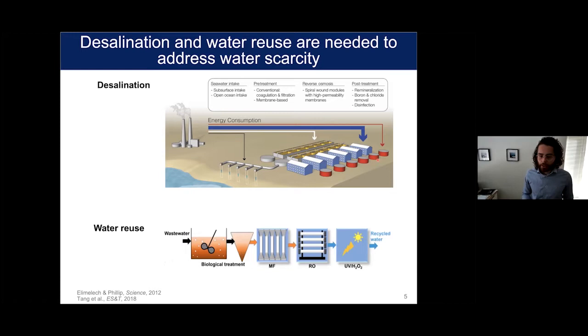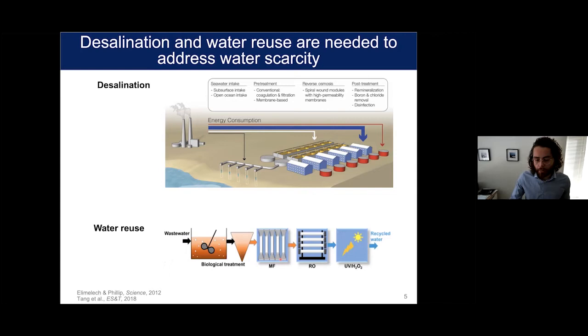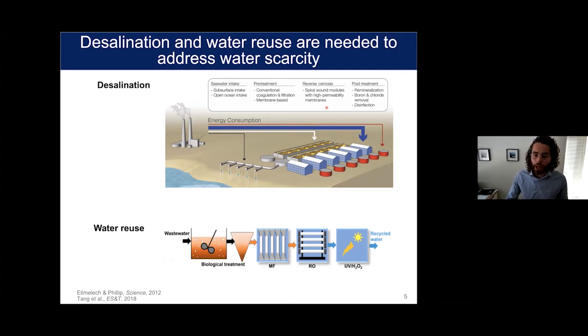Water reuse is also a great option — in many ways it's a better option than desalination. We can take wastewater and consider using it for direct potable, indirect potable, or agricultural use. One treatment train of wastewater reuse involves conventional wastewater treatment followed by microfiltration, RO, and then advanced oxidation. For both desalination and water reuse, the key is to be able to remove almost everything — salts and contaminants — and for this, reverse osmosis is really well suited. Most new desalination facilities and standard water reuse configurations use RO.